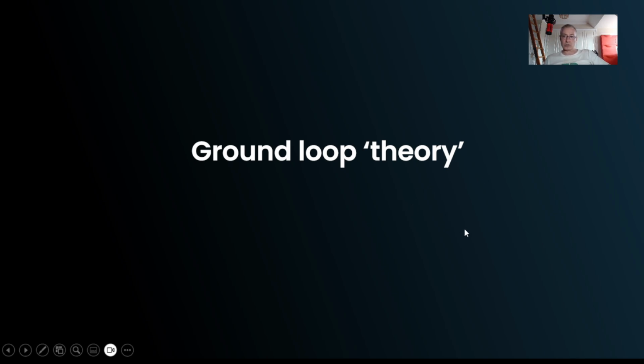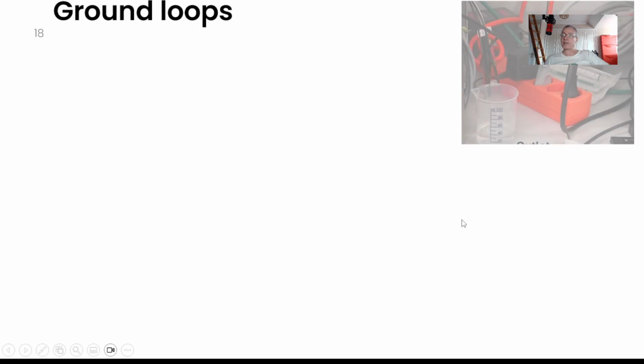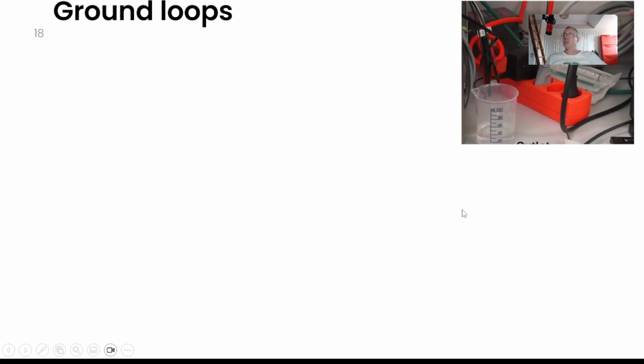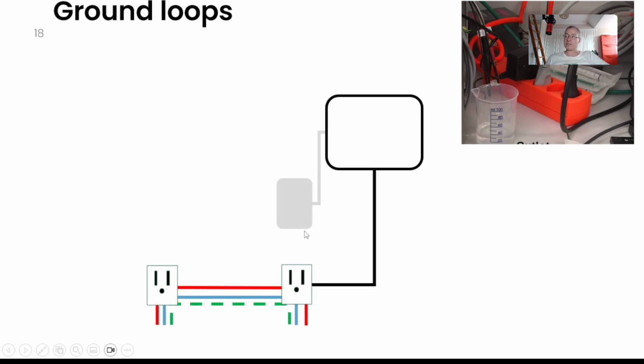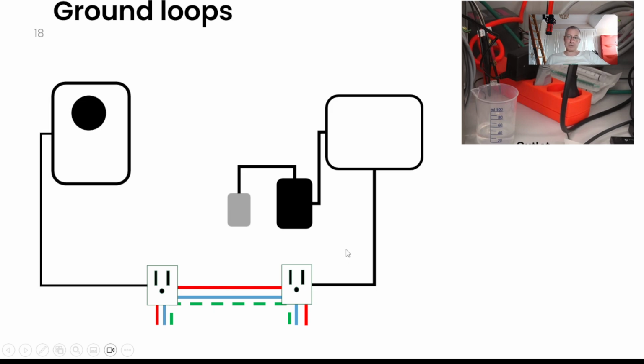There's also something that's a bit more convoluted, the ground loop theory, that I've thought about. I've seen this in the past. You've got a couple of electrical items plugged in. Great, there's no issue with that. You've got the PC, which through its USB-C or USB is in connection with the potentiostat. The potentiostat is in electrical contact with a flow cell, and you have a pump system. The pump system is pulling solution from the reservoir through the flow cell and sending it to waste. This line here means that these two electrical systems are actually in contact with each other. This is kind of ionic contact.